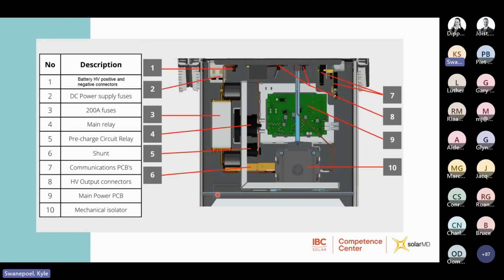This is the top view of what the BMU looks like inside. You've got your positive and negative connectors over here. You've got your positive and negative fuses, both sitting on top of each other here. This is where your protection is. If you have an overcurrent event and the fuse blows, this is the fuse that will blow. It is easily accessible, just taking off the top lid of the BMU to get to the fuse. And that will obviously be changed when the battery is off.